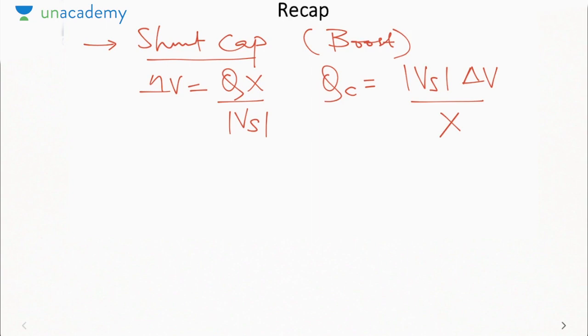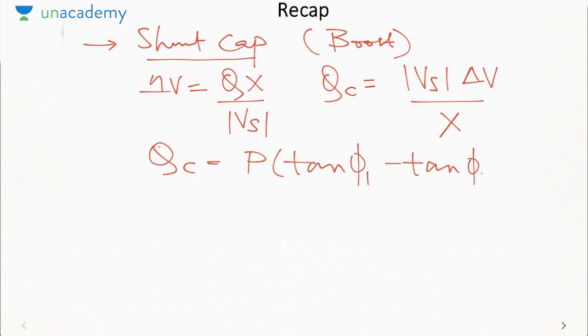So it is used in case of a lagging power factor load. We saw it can also be used for power factor correction, and QC was given by tan phi 1 minus tan phi 2, where phi 1 is the initial power factor angle and phi 2 is the corrected power factor angle. Then we saw the shunt inductor.